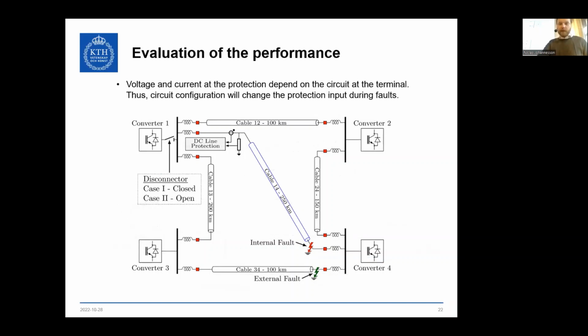So in order to test this, I put together some simulations. In a multi-terminal network, you will always have some kind of flexibility, so you can have different configurations. So I tried to disconnect one of the converters, then simulating internal and external faults, because ideally we don't want different behaviors of the protections, and that comes back to this dependability.